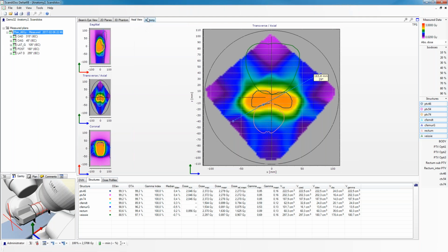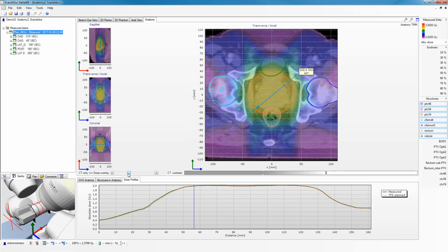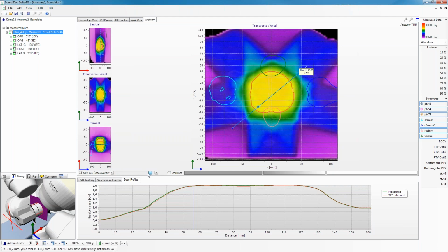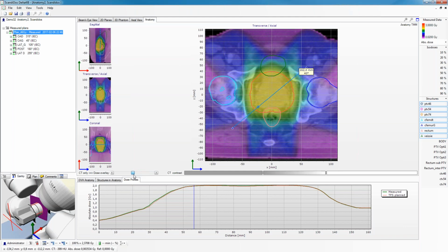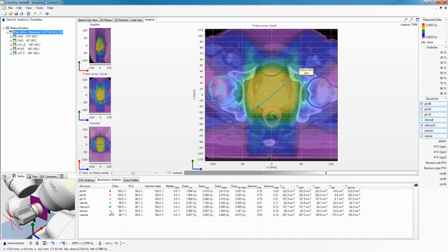In analogy to axial view, I have the anatomy tab, which is going to display data to me in the same format as axial view, but the anatomy data is actually calculated inside the patient geometry, whereas the axial view data is calculated inside the phantom geometry. So what I can see here is the patient CT, and then the measured dose displayed over the patient CT. I can still see all of my structures. I can look at profiles. I can look at dose volume histograms, and I can get the analysis: the gamma index, distance to agreement, and dose deviation inside these different structures. So this is the data that is available to you when you are using the Delta4 software.